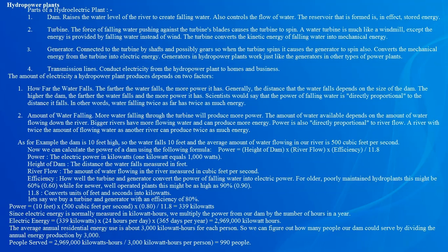2,969,000 kilowatt hours. The average annual residential energy use is about 3,000 kilowatt hours for each person. So we can figure out how many people our dam could serve by dividing the annual energy production by 3,000. People served equals 2,969,000 kilowatt hours divided by 3,000 kilowatt hours per person equals 990 people.